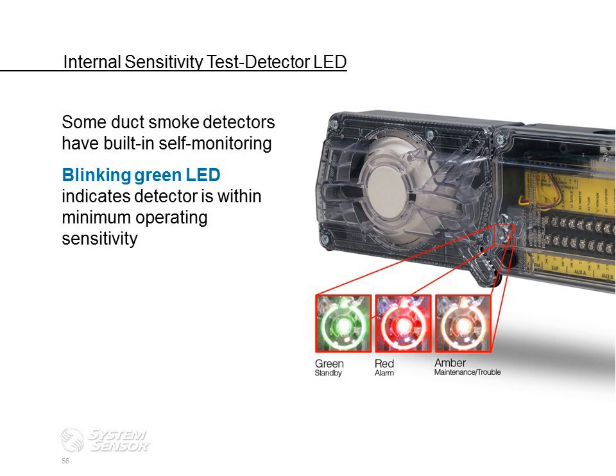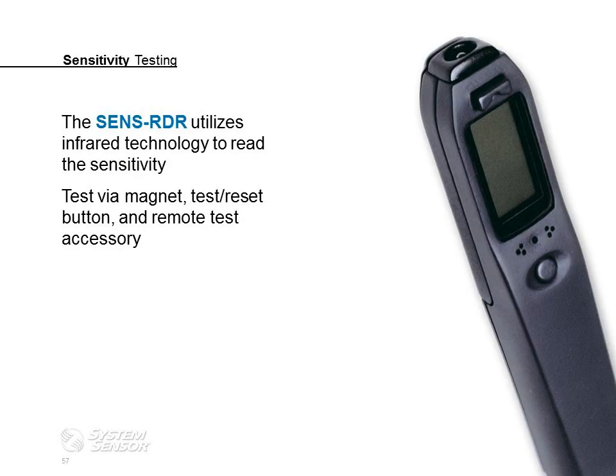Now, our product also has an internal sensitivity test, and you can read it through the LED, because you remember we talked about NFPA standards requiring that sensitivity test one year after acceptance and then every other year. Our detector has it built in for self-monitoring. The blinking green LED indicates that our detector is operating within the required sensitivity threshold. But if you are in a situation where you need an actual reading, we offer our sense reader, our SENS-RDR. It utilizes infrared technology to read the sensitivity.